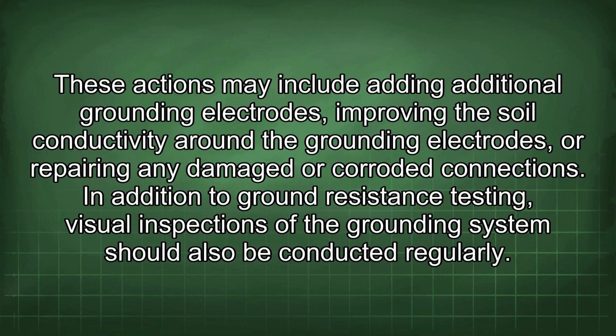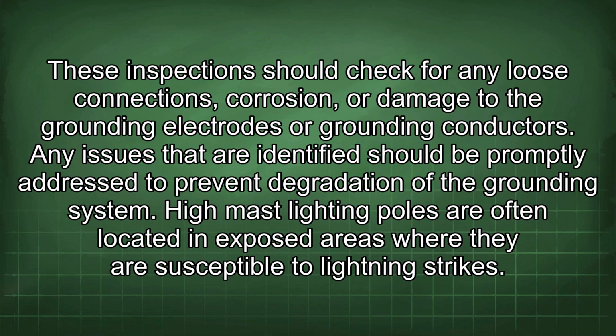or corroded connections. In addition to ground resistance testing, visual inspections of the grounding system should also be conducted regularly. These inspections should check for any loose connections, corrosion, or damage to the grounding electrodes or grounding conductors. Any issues that are identified should be promptly addressed to prevent degradation of the grounding system.